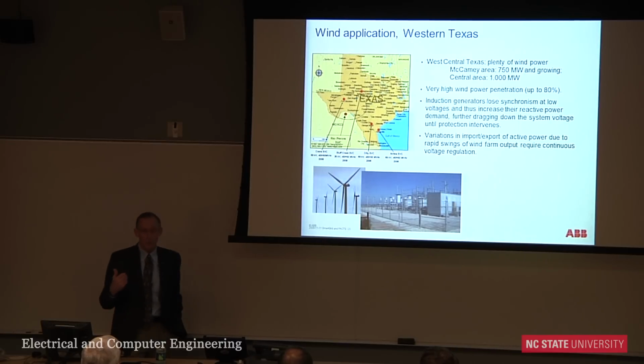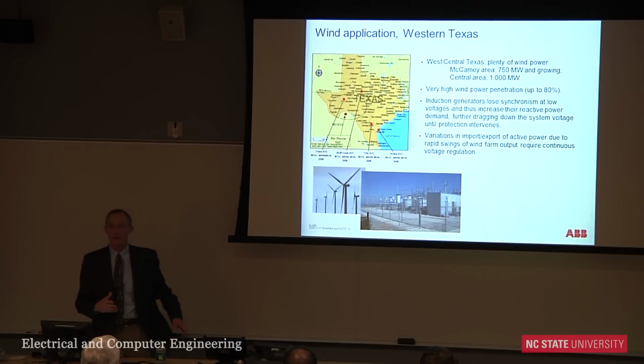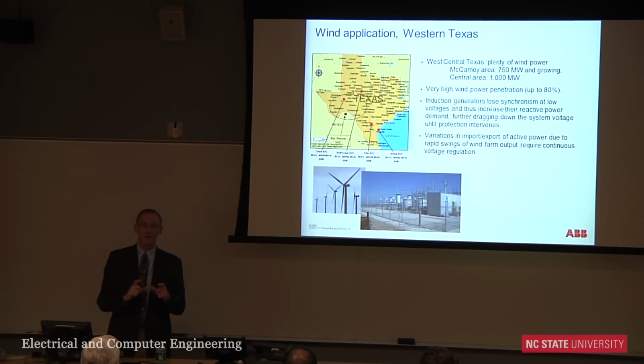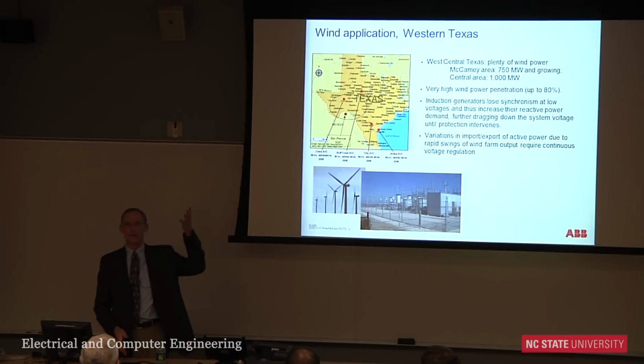Static VAR compensators address one of three limitations in power transfer across a transmission line. The first is voltage regulation, you can't have the voltage at one end significantly out of whack with the far end. Too much voltage regulation is not a good thing.